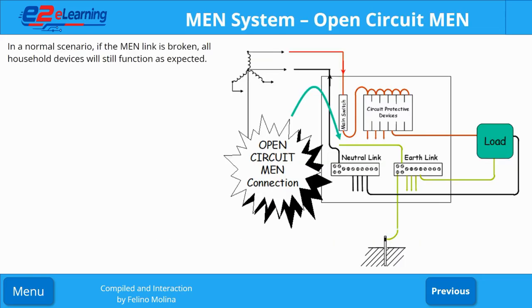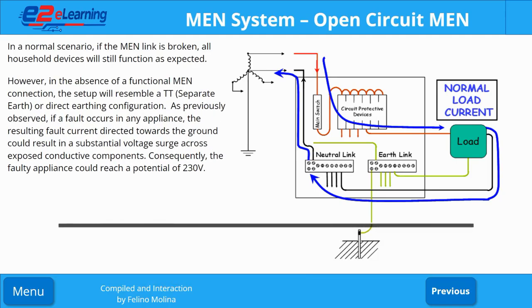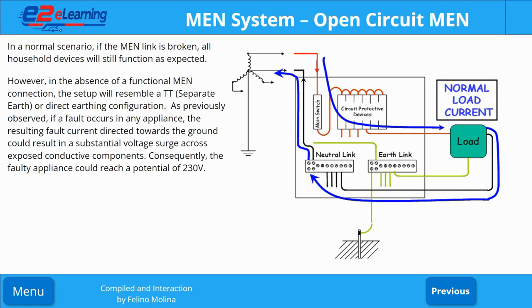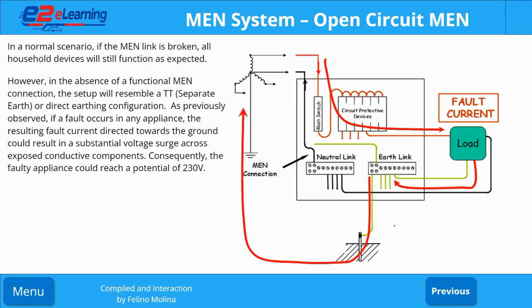In a normal scenario, if the MEN link is broken, all household devices will still function as expected. However, in the absence of a functional MEN connection, the setup will resemble a TT or direct earthing configuration. As previously observed, if a fault occurs in any appliance, the resulting fault current directed towards the ground could result in a substantial voltage surge across exposed conductive components. Consequently, the faulty appliance could reach a potential of 230 volts.